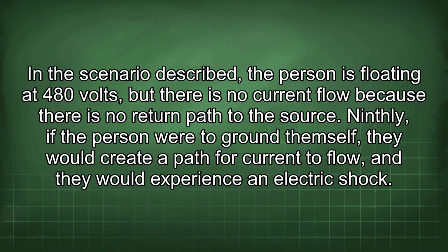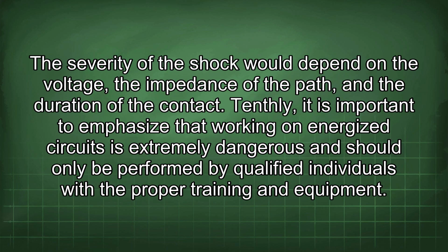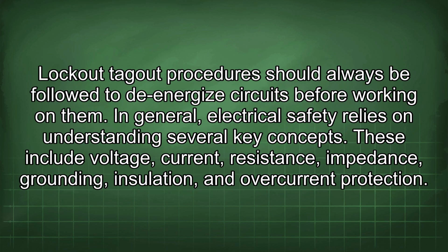Ninthly, if the person were to ground themselves, they would create a path for current to flow, and they would experience an electric shock. The severity of the shock would depend on the voltage, the impedance of the path, and the duration of the contact. Tenthly, it is important to emphasize that working on energized circuits is extremely dangerous and should only be performed by qualified individuals with the proper training and equipment. Lockout-tagout procedures should always be followed to de-energize circuits before working on them.